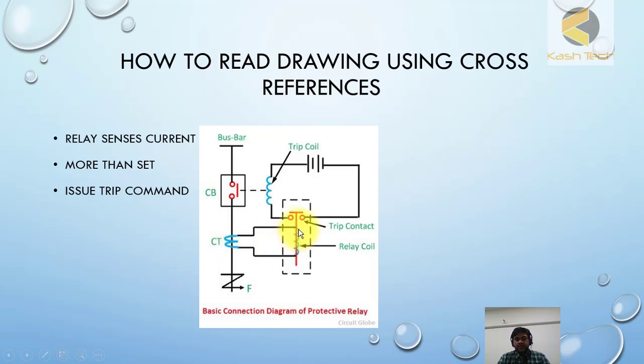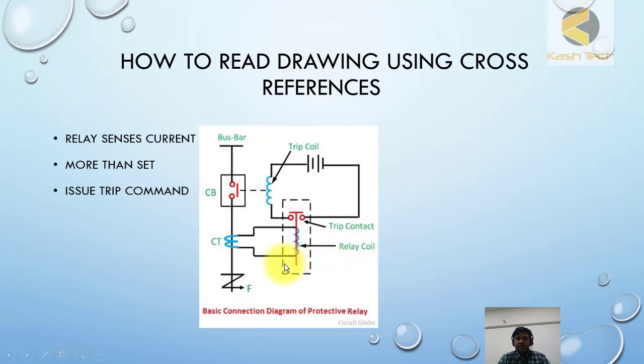Sometimes a relay does not give a trip command directly to the coil. Instead, it operates an intermediate relay and tripping is initiated through that relay's auxiliary contact. These intermediate relays are called tripping relays, and the relay which is sensing the fault and operating the tripping relay is called the main relay.